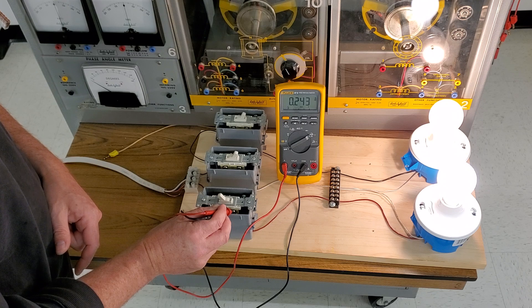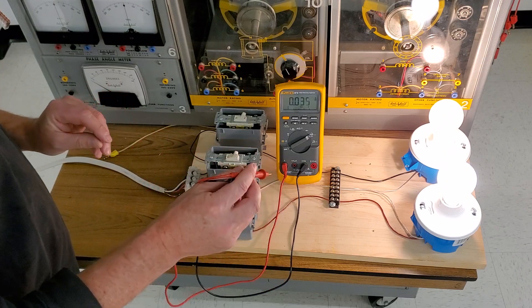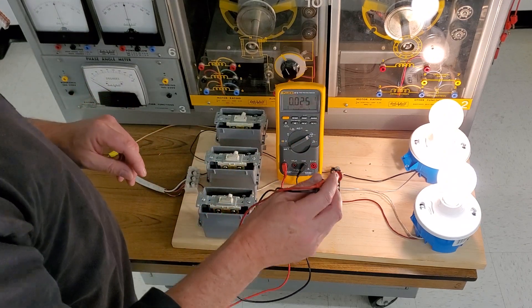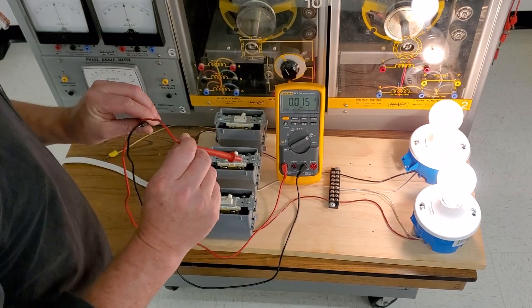The other thing that a lot of people don't realize in a multi-wire branch circuit like this is if this is a single phase, since we're balanced across these two loads, we'd actually be reading near zero amps on the neutral.